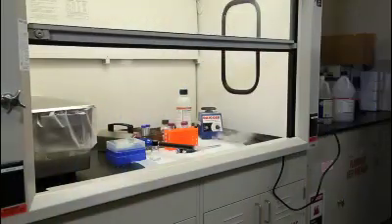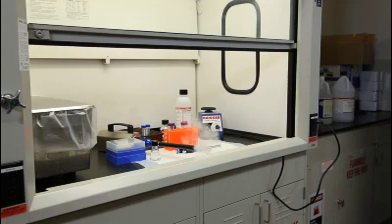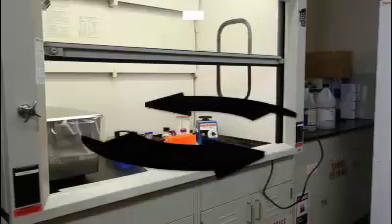When a person walks in front of an open fume hood, the vortices can overcome the fume hood face velocity and pull contaminants out of the fume hood into the vortex and into the laboratory.